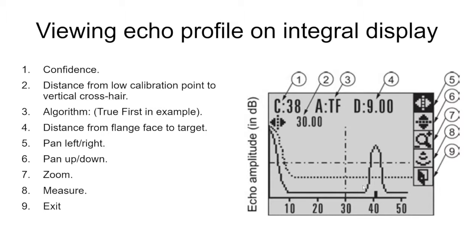Now that we've pulled up an echo profile on the screen, what does this all mean? Looking at the upper left hand corner, the number C:38 shows us the confidence is 38.